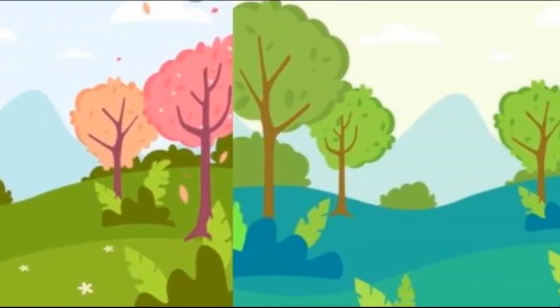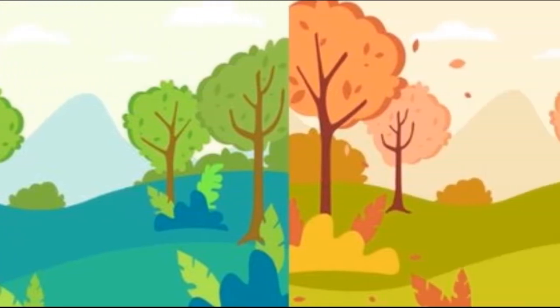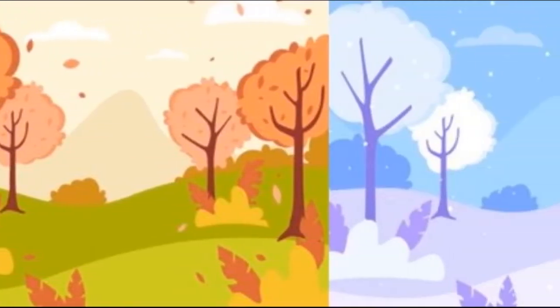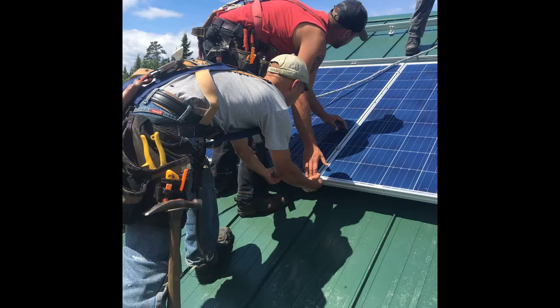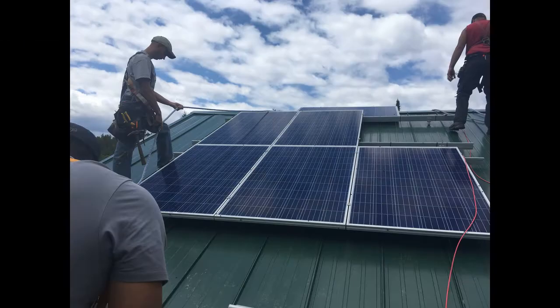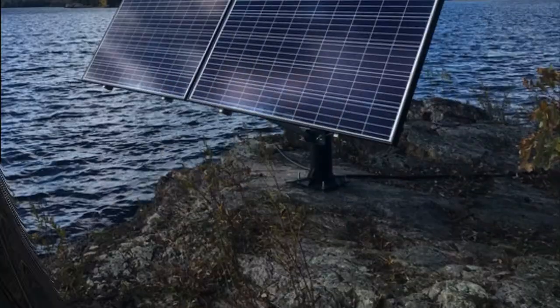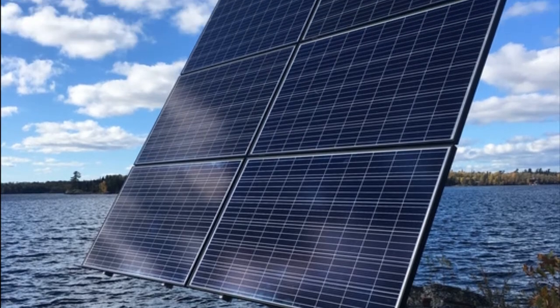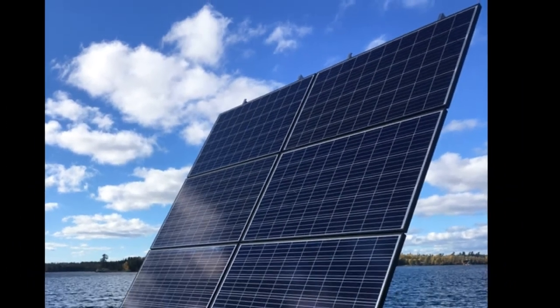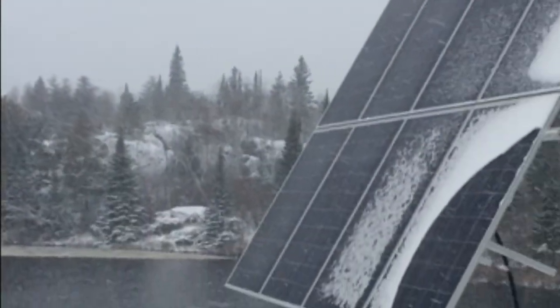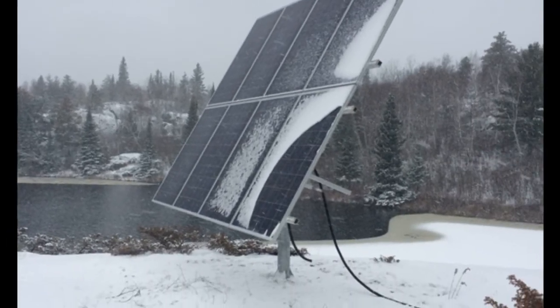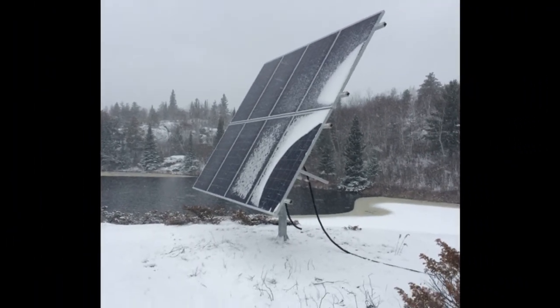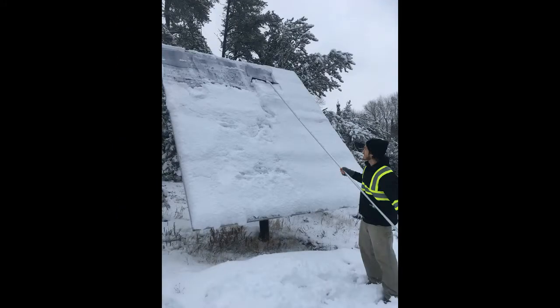We consider the occupancy and seasonal usage patterns to form a better understanding of the conditions that the system will need to perform in. Roof-mounted solar PV systems are typically geared toward three-season use, while top-of-pole ground-mounted systems are ideal for four-season applications. Off-grid solar PV in Canada brings with it its own set of challenges. For winter operation, snow can cover your solar PV panels, the days are shorter, and the sun is lower in the sky, requiring a more steeply sloped, southern-facing array.